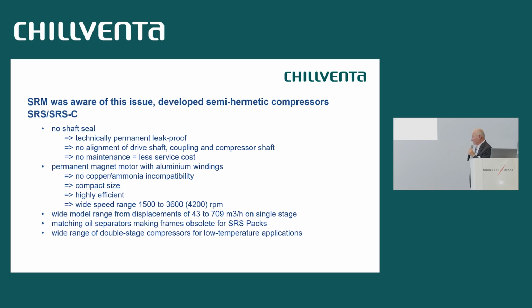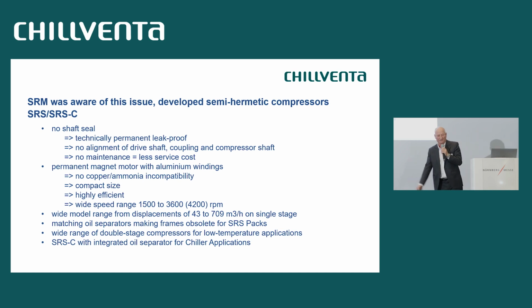We have got a wide range of double-stage compressors for low-temperature applications as well, semi-hermetic. And with our SRSC, like compact or like chiller, we have a compressor which has an integrated oil separator. So we went one step ahead. This, again, is reducing cost of the oil separator, of the piping up, of the welding, and of potential leakages.